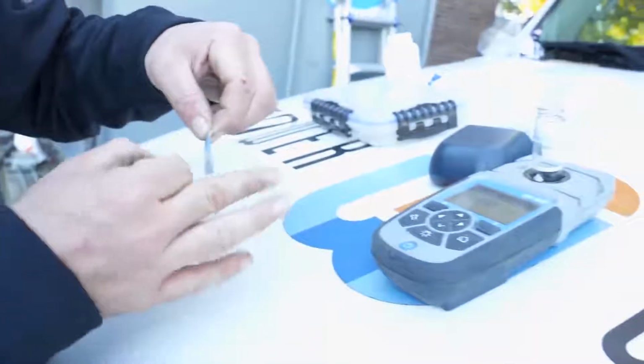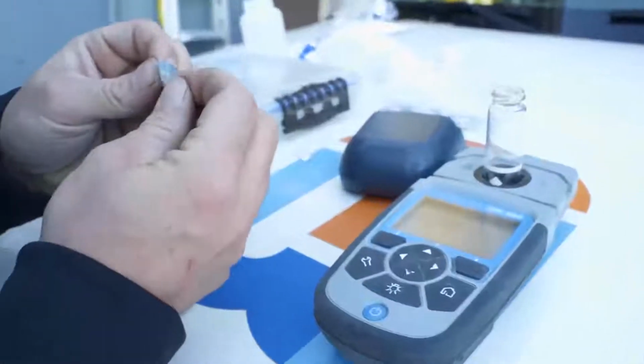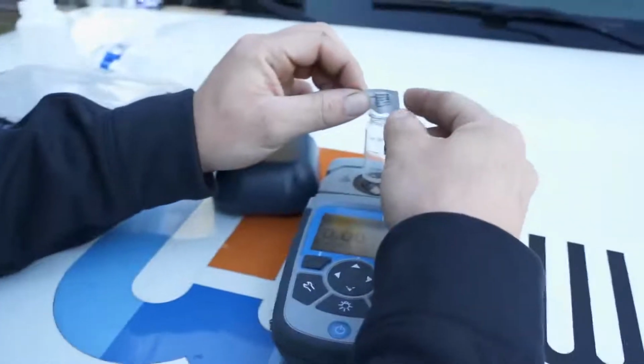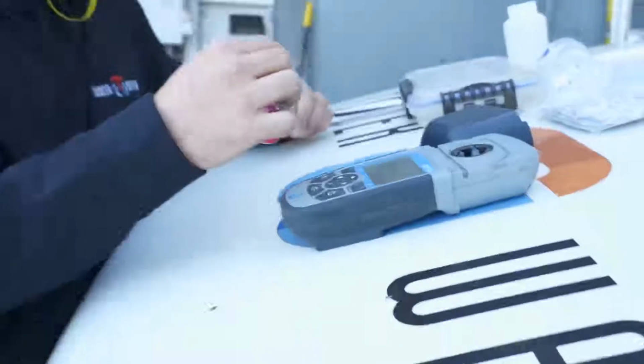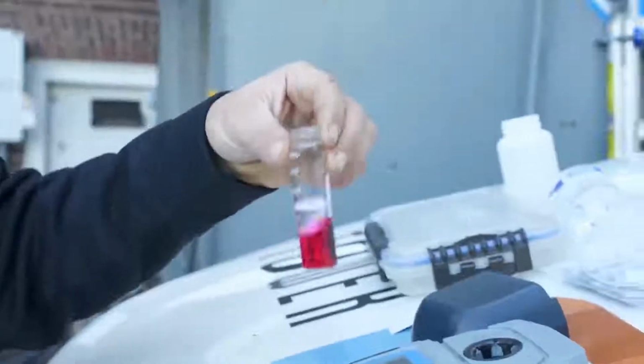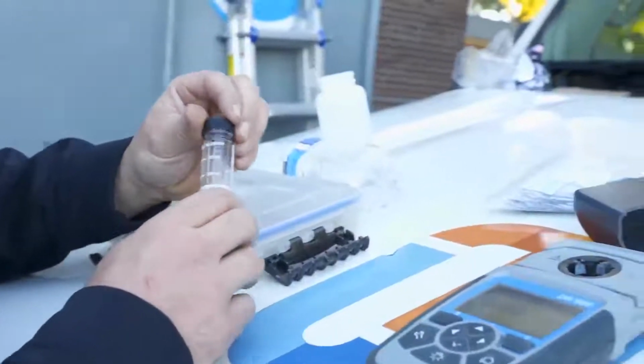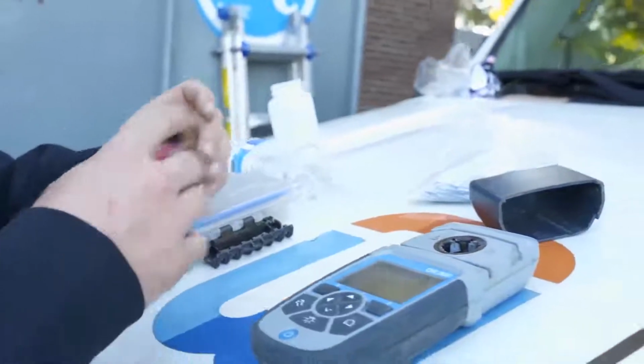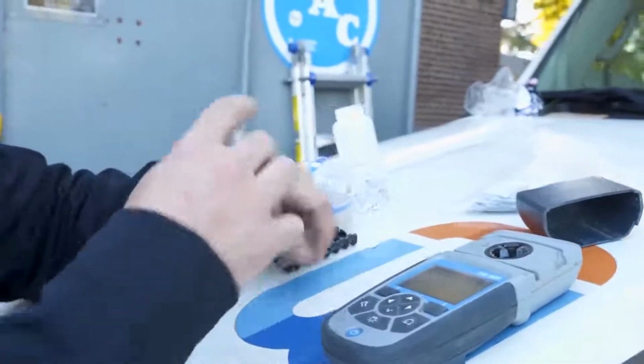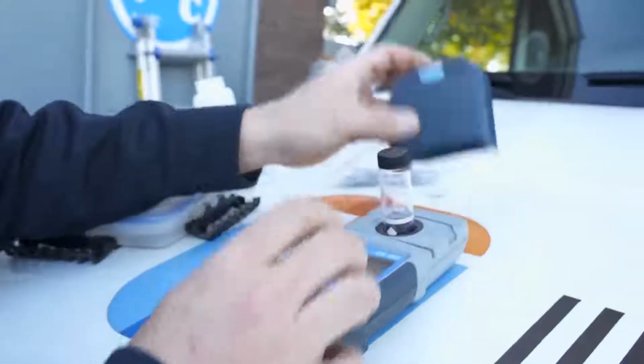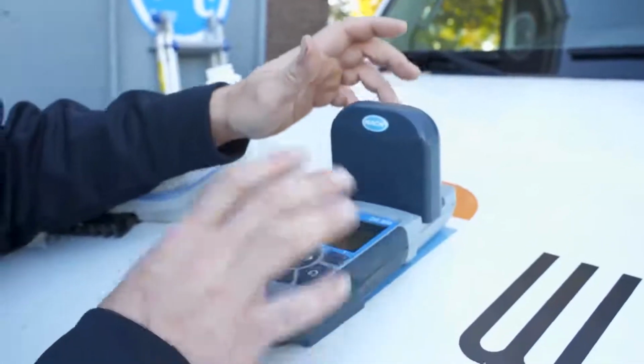Test the water, making sure all disinfection levels, including pH and free chlorine, are at least at the minimum ranges. This should be conducted every 15 minutes for the first hour before beginning the actual cleaning. This proves that the chemical addition was effective, as is for your safety, and part of the Legionella requirement to kill nearly all bacteria and Legionella in the system. These chemicals also help to interrupt any biofilm, which can entrap dirt and debris within the system.